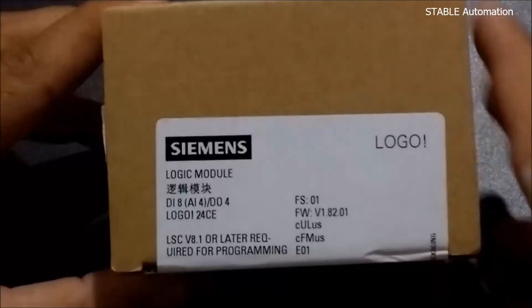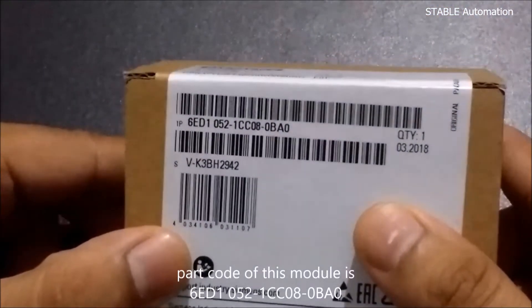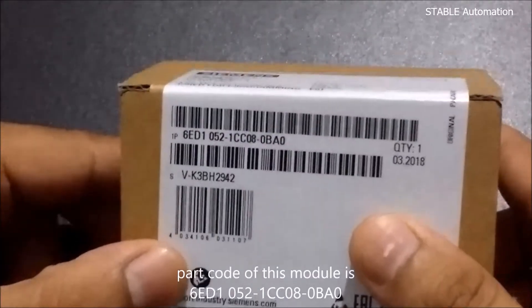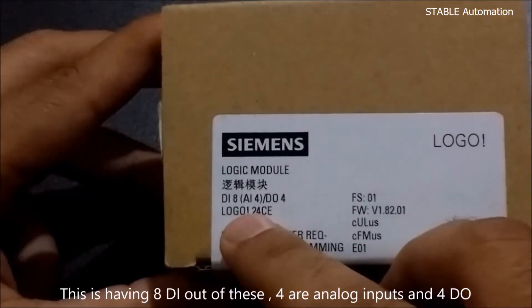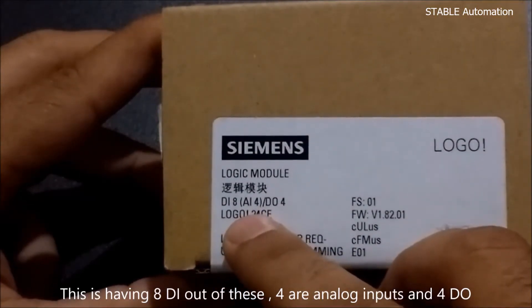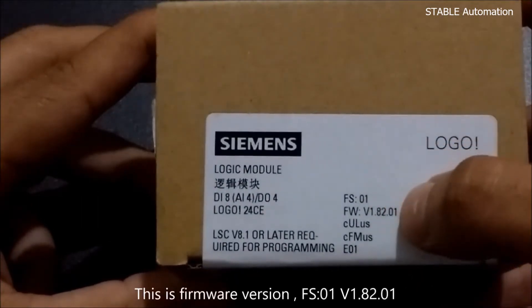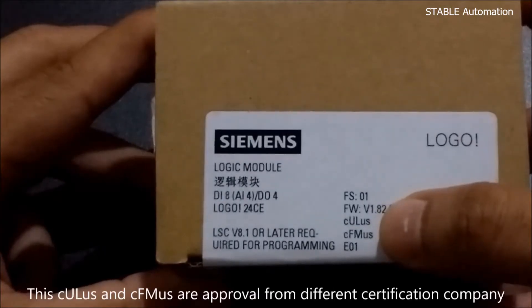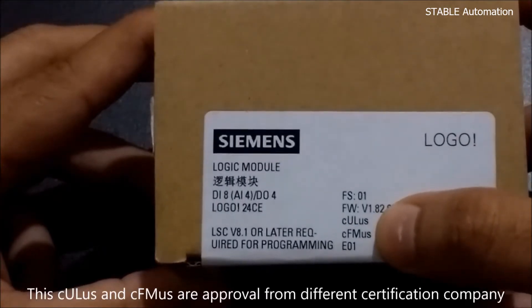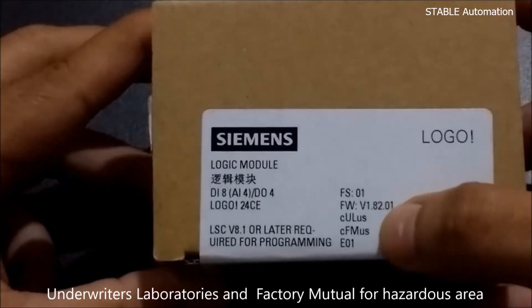The part code of this module is 6ED1 052-1CC08-0BA0. This is having 8 DI, out of which 4 are analog inputs and 4 DO. The firmware version is FS01 V1.82.01. CULUS and FMUS are the approvals from different certification companies — Underwriters Laboratories and Factory Mutual — for hazardous area.